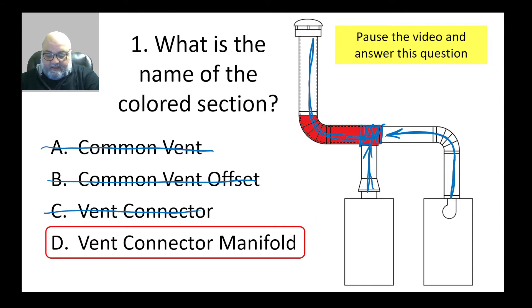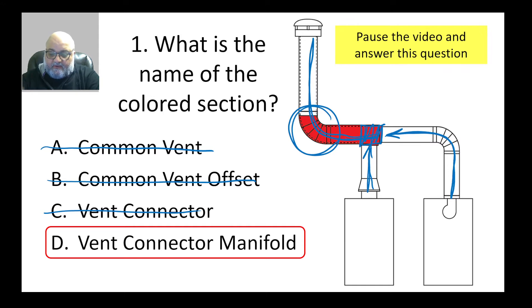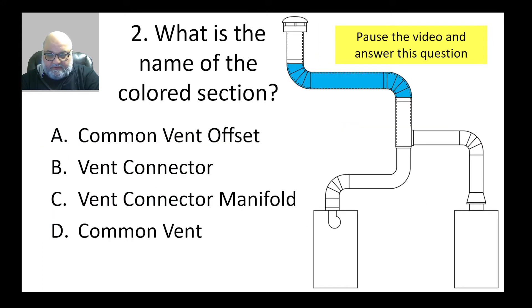That leaves us with the only correct answer: vent connector manifold. I could also tell because there is only one elbow in the main vent — just one elbow — which is a definitive indication that this is not an offset but a manifold.